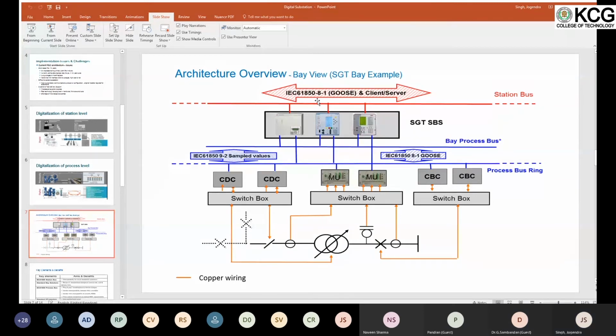What will be the specification, like the Vk, Imag and all that, that you have in conventional CTs? Yeah, that is not required for the optical CT. I don't know the specification myself, but for the protection optical CT you don't need any knee point voltage, magnetizing current, etc., because it is converting to digital signals, digital waveforms.